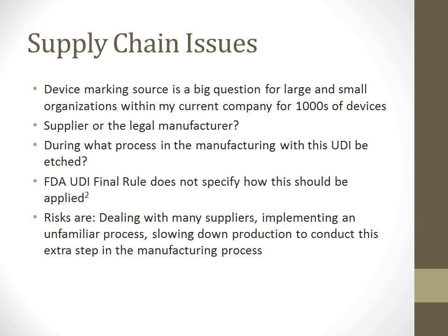I know a lot of other companies are probably looking at the same thing. FDA's UDI final rule does not specify how this UDI should be applied, so it's kind of open-ended, and there's no real guidance around this device marking requirement. Some of the risks are dealing with many suppliers, implementing an unfamiliar process with a lot of these suppliers, or with us as a current manufacturer. Another risk is slowing down production to conduct this extra step in the manufacturing process.